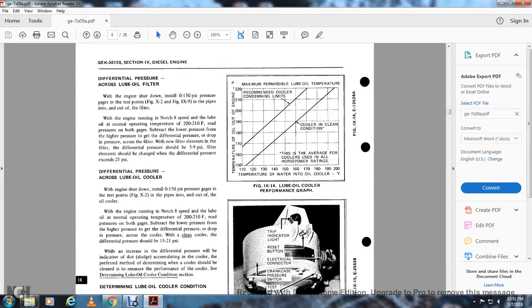Figure 9-14 shows the lube oil cooler performance graph: the Y-axis is temperature of oil out of the engine (155 to 220°F maximum permissible), and the X-axis is temperature of the water in the oil cooler. Curves shown are: recommended cooler condemning limits, cooler in clean condition (the average of coolers used at full horsepower ratings). To perform the test, install an accurate 250°F temperature gauge at each of the specified measurement points.